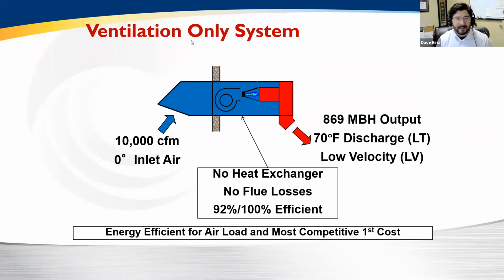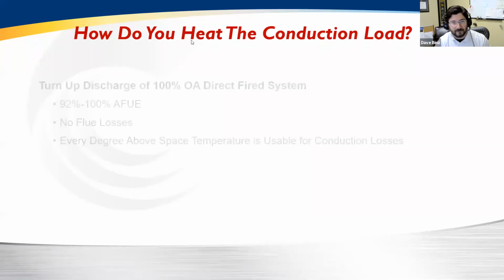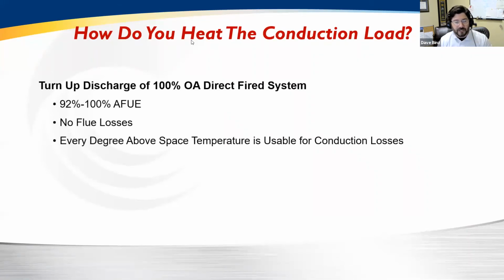This is why 95% of all kitchen systems utilize this exact technology. Low cost, fairly simple system, high reliability, and extremely energy efficient because it's got to run all the time to meet my ventilation loads. Now, the second thing that we have in large warehouses and buildings is it's not just the ventilation load. What about my conductive load? How do we heat the skin losses, or those conductive loads, from that cold outside and warm inside?